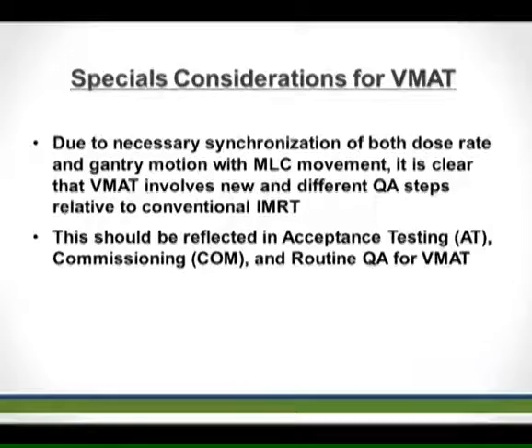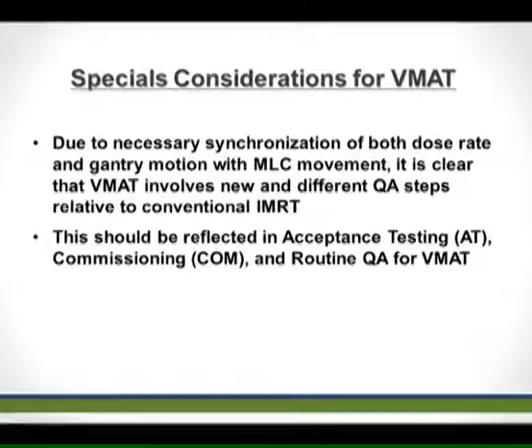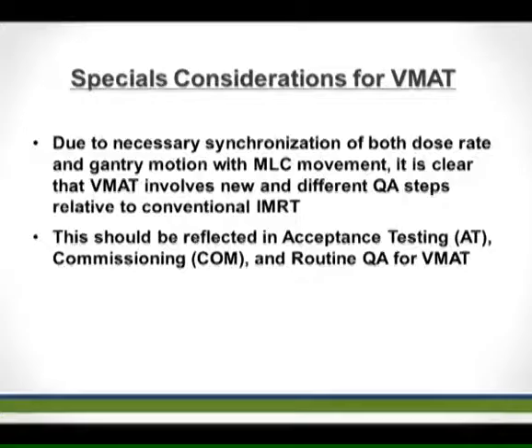Dr. Ying gave an excellent talk on QA. The special considerations for VMAT stem from its many changing variables: gantry movement, dose rate change, and MLC movement. All of these need to be tested individually and in combination during acceptance testing, commissioning, and routine QA of VMAT.